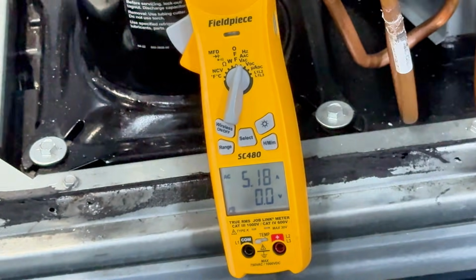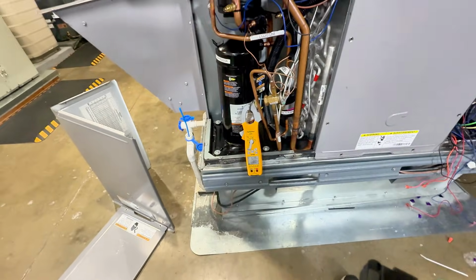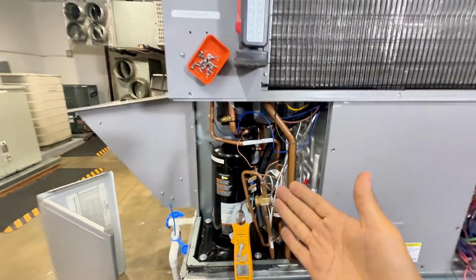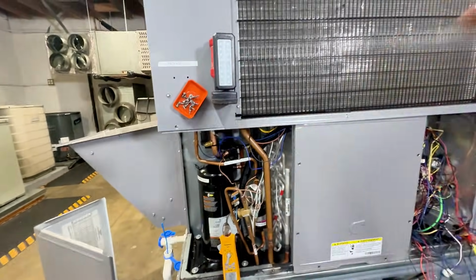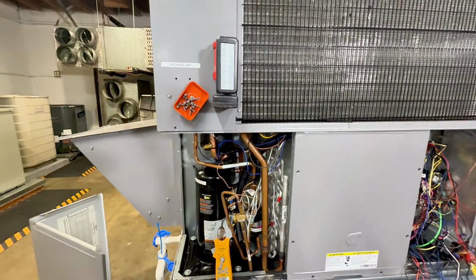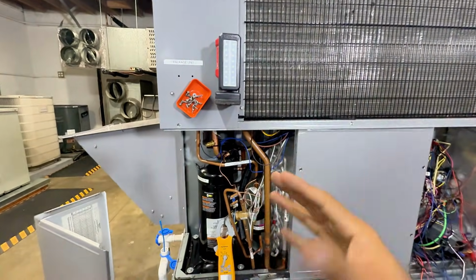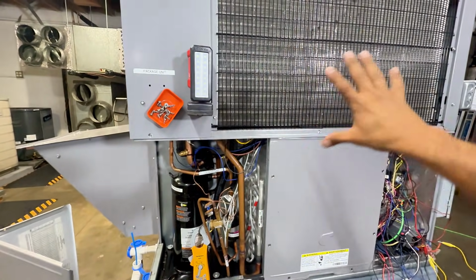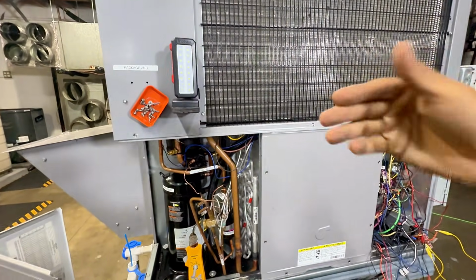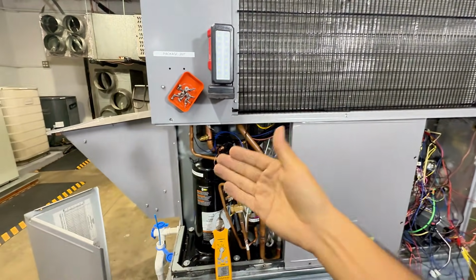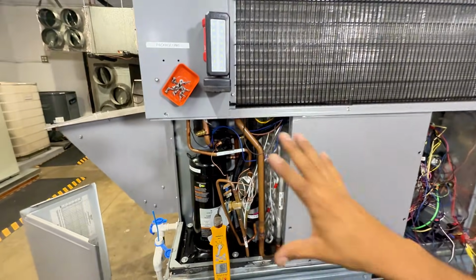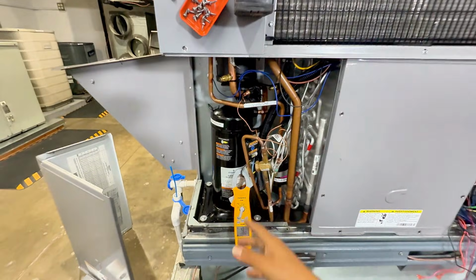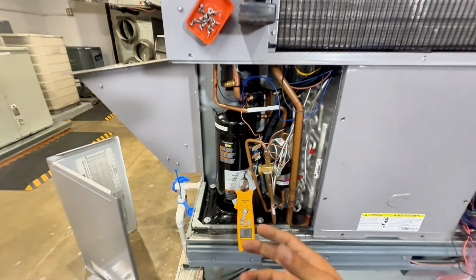So yes, compressor amperage can fluctuate based on what's going on with the system. A lot of factors can happen. That is why keeping the condenser coil clean, the filters, and making sure it's properly charged all play a part in how much current that compressor is going to be drawing.